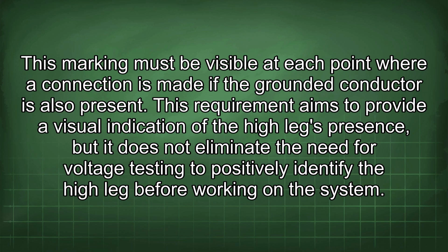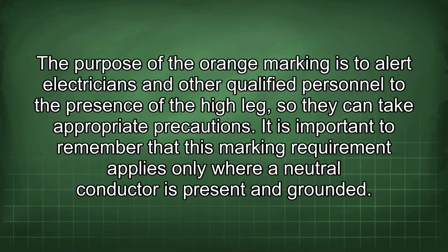This requirement aims to provide a visual indication of the high leg's presence, but it does not eliminate the need for voltage testing to positively identify the high leg before working on the system. The purpose of the orange marking is to alert electricians and other qualified personnel to the presence of the high leg, so they can take appropriate precautions.